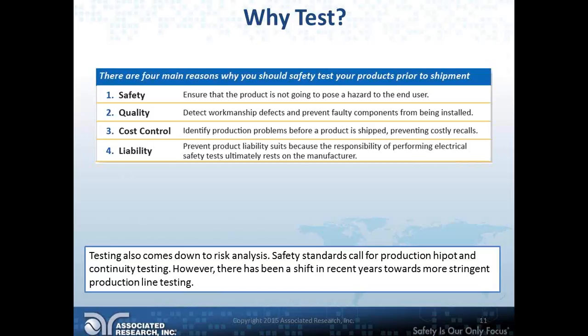You've also probably all dealt with a safety standard. If you haven't, a safety standard is basically the standard that tells you, for your type of product, what tests you need to run. For example, if I'm testing a vacuum cleaner for home use, I'll test to IEC or UL 60335 for household appliances, which calls for a leakage test, a hipot test, and a ground continuity test. There's a big difference between type testing, which is done in a lab on a prototype you're still working on, and production testing, where every single product going out the door gets tested to make sure it's safe.